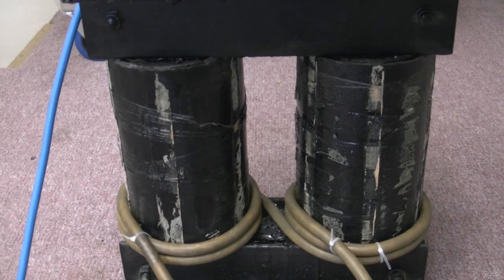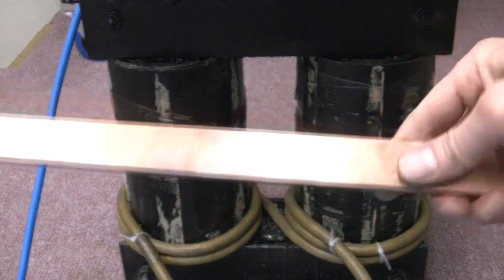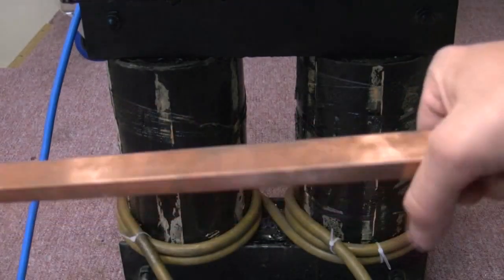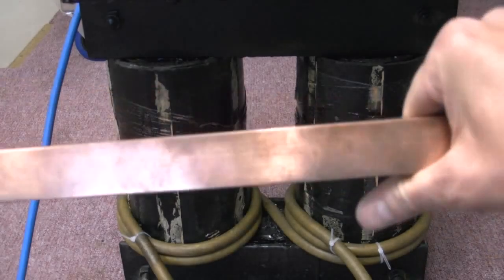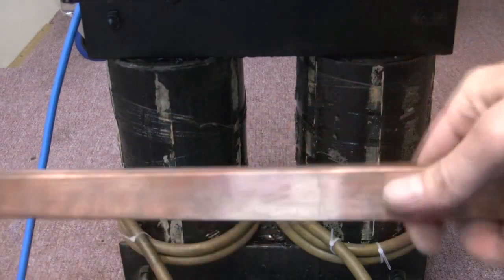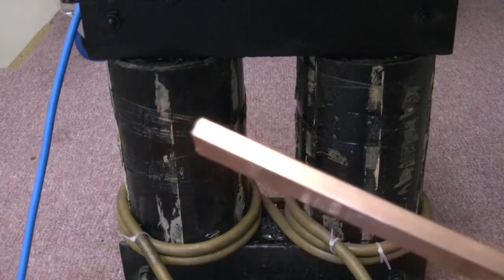My clamp meter won't be able to register it - it will be well over 10,000 amps, which is quite a lot. This bit of bar will just glow red and pop like a bit of 5 amp fuse wire on a cooker, and that's what we want.